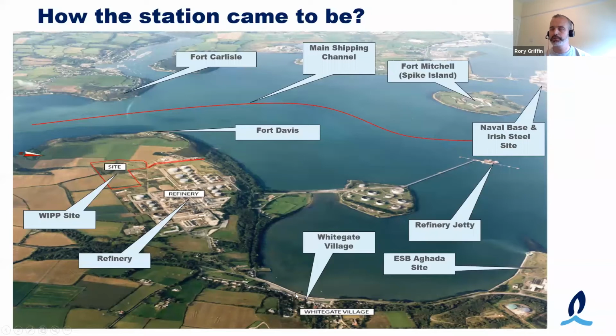The one thing that was missing was a decent gas connection down to the Whitegate area. Up the road at Middleton is quite a strategic node on the gas network. You have the compressor station there, which I suppose historically was used to pump gas into the Kinsale field in the summer months and take it out again in the winter. So ESB and Bord Gáis Éireann developed a pipeline down to support the two new units.